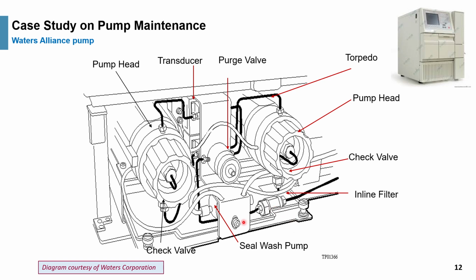Here's the inline filter. Here is the seal pump wash, which is a peristaltic pump that allows you to wash behind the piston if you're using ion exchange chromatography with high salt. Here is the purge valve, which you can open manually for dry pumping. If the pump is dry, the pump would not be able to pump liquid, so you have to draw out manually 10 milliliters of solvent to make sure the pump is wet. And also for the Alliance, you need to do wet prime quite a bit before you do your sample injection. Here is the pressure transducer.